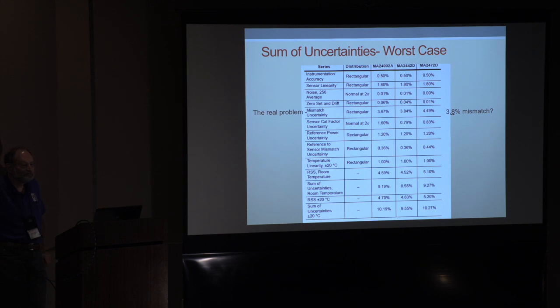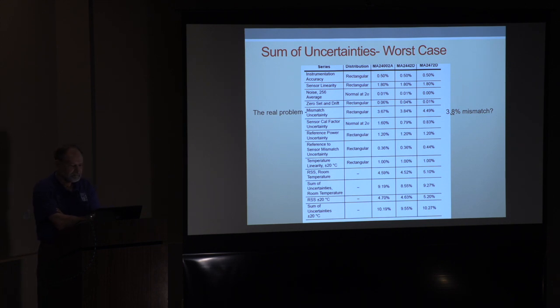Noise average and zero set are quite small, but mismatch uncertainty is almost 4%. That's the bugaboo. And it's not just the mismatch uncertainty of the load, like if you're measuring a dummy load, for instance, or a power meter that's 49.7 ohms. That's only half the problem. The other half is what you're measuring it with. Both sides need to be measured in order to get a true picture of what the mismatch uncertainty is, and you cannot assume a thing. Reference power uncertainty is 1.2%. I think that's a little high. But you can read down there, and that adds up to quite a bit of inaccuracy.